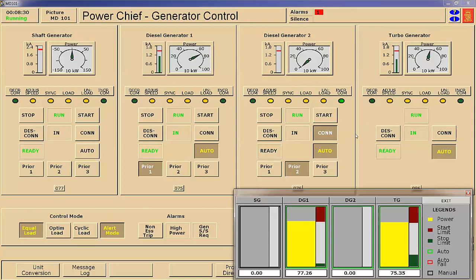You see another generator. So another generator is required. It is started, number 2, and they will automatically connect it up. So this is your power management system. It saw an increase of load required, and it automatically puts the generator on the line. It's connected, or it's connecting now, I'm sorry. So now we'll have 3 generators on the line, and it's going to balance the load between them.